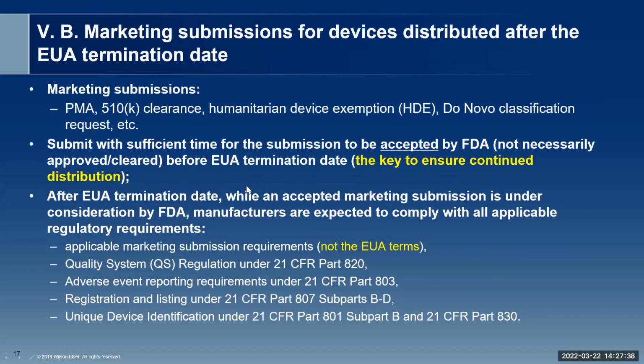So we talked about notification of intent. The next subsection, section V, subsection B, is marketing submissions for devices distributed after the EUA termination date. Regardless of what type of device you have, if you intend to continue marketing your device after the EUA termination date, you need to submit your marketing submission, which is either a 510(k) clearance, a PMA application, or any other type of marketing submission, such as an HDE or de novo classification request, etc.